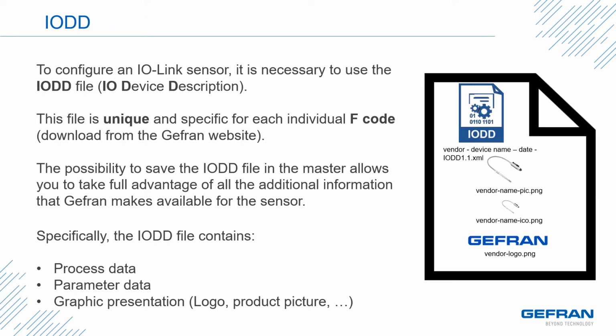The IO-Link device description file is an electronic file that is actually the heart of the IO-Link system. This file is unique to every individual model code that Gefran creates. And this file contains all of the description, information, and identification data that was discussed earlier in the presentation. This file is stored in the master, and it is key to allow the master to identify and connect to the sensor when it's plugged in to a port of the master. It's also used by the master to make sure that the sensor plugged into that port in fact matches the data described in this file.